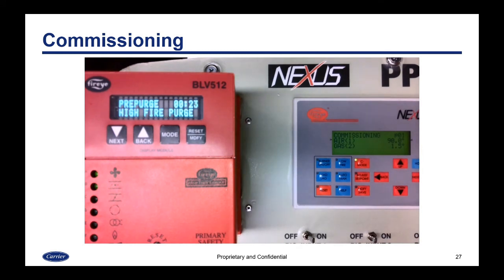Then when I hit next, it's going to actually begin the purge and send the feedback. So it's going to go through the purge like it did before, and then it's going to send the command to drive to the ignition position, and that's when we have to set the ignition position. So the Flame Safeguard doesn't really know what's going on. It's still sending and receiving the right commands. We're just delaying when we send the feedback until we've finished setting up the position we're trying to set. So now it went to point 2, and now we set the ignition position. So first it's driving down to where it was already set for, so that I can then tune it. When it's done moving, I'll have a star next to P2 indicating that I can set it.